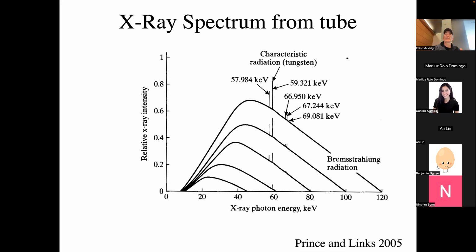The stopping power for low energy of most materials is quite high. And so they just don't make it out, right? The other thing we can do is we often put a piece of copper or aluminum right in the way of the beam of X-rays, and it's a very thin piece, and it filters out many more of these low energy X-rays.